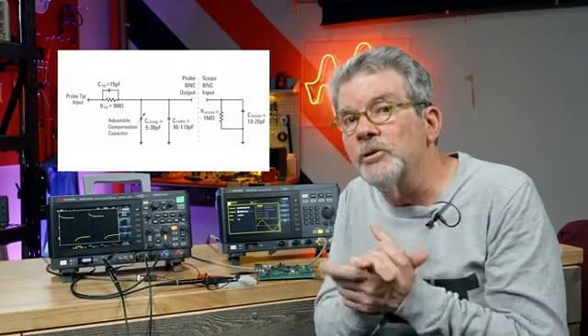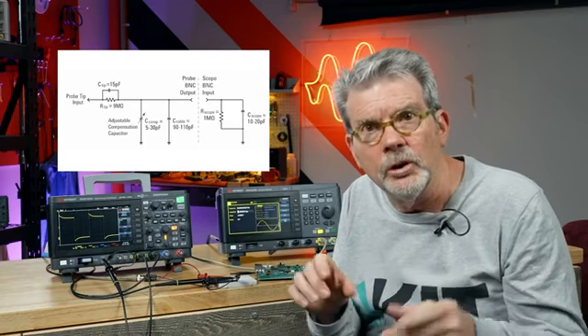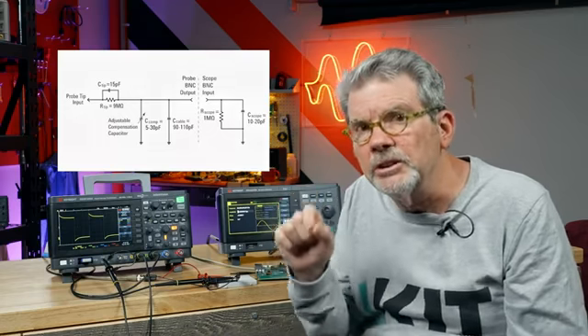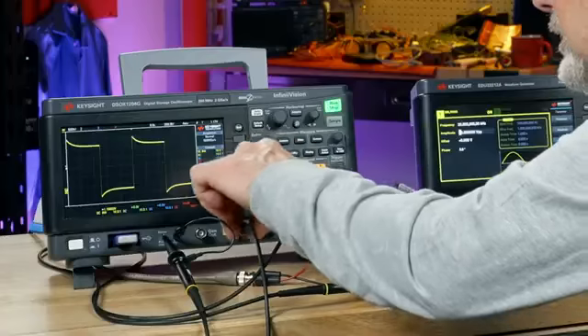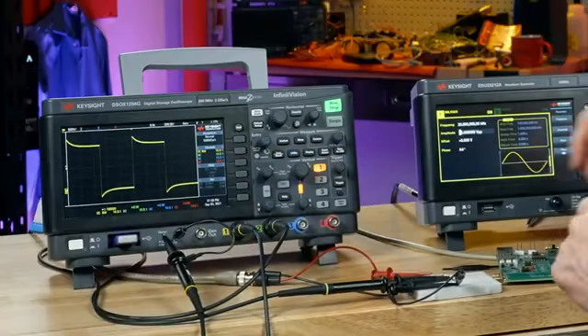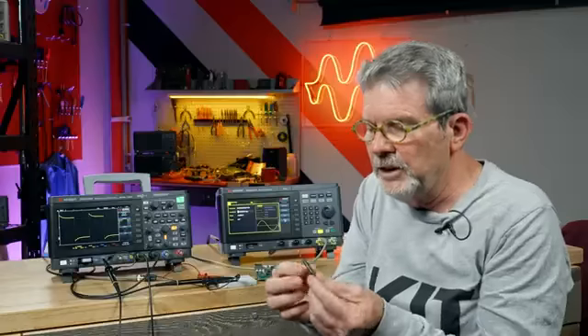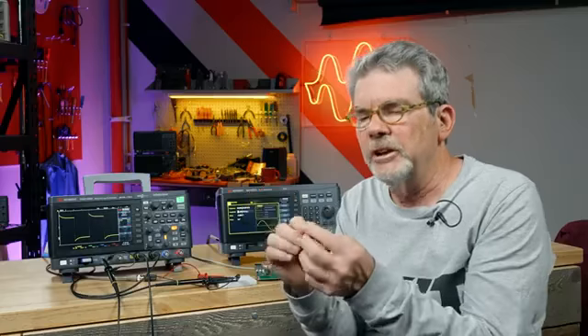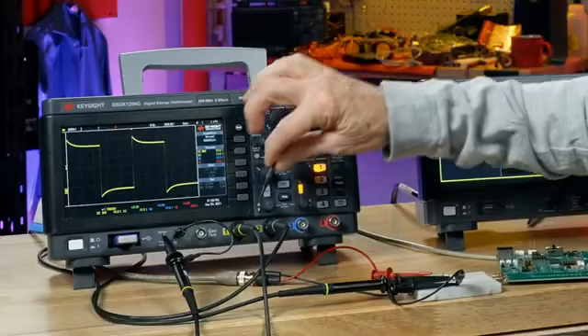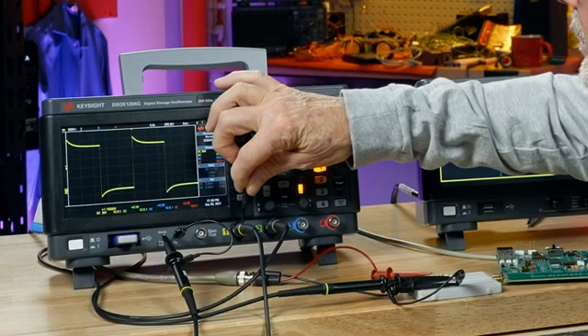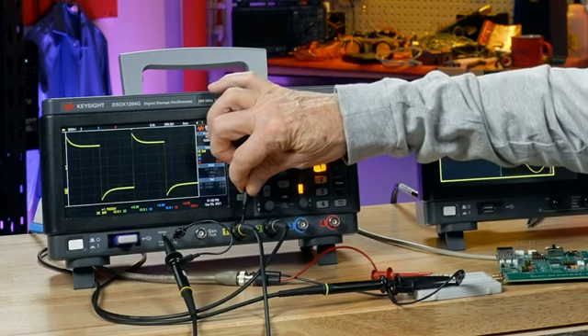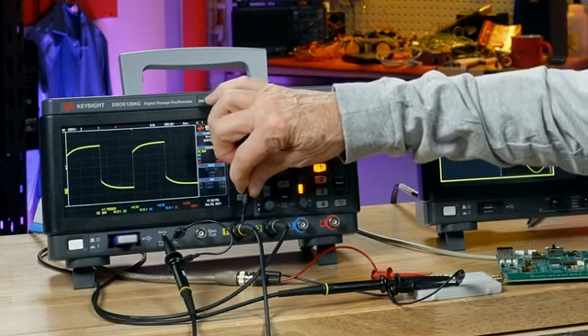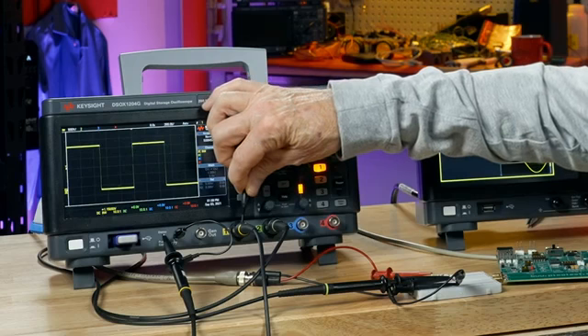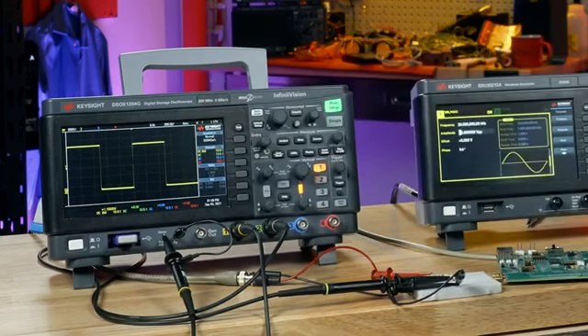If you remember from that high frequency model of the probe, there's a variable capacitor inside the probe, and there's an adjustment near the base of the probe, and your probe should come with an adjustment tool. This looks like some sort of hex drive. You just insert it in there. There's more overcompensation. There's undercompensation. And now it looks like a true square wave. Now this probe is calibrated.